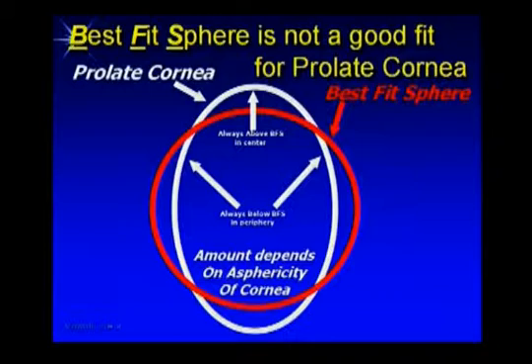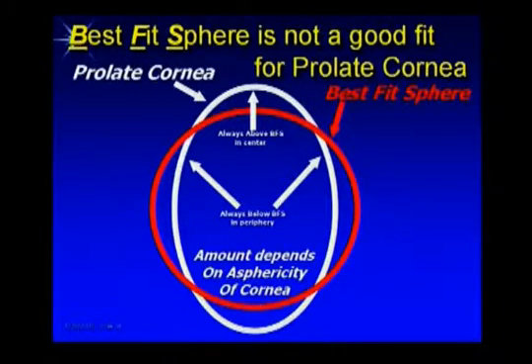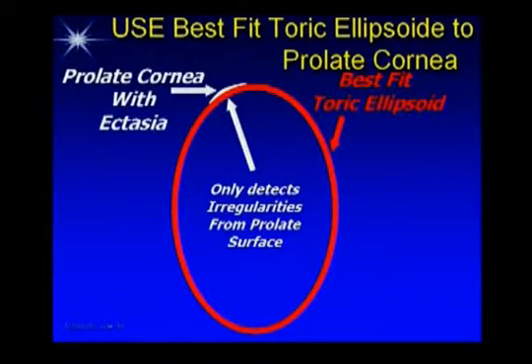For 25 years we've used a sphere as the reference for elevation above and below when looking at corneal data. But the cornea is not a sphere — it's an ellipse, an oval or football shape. Because we've used a sphere, trying to fit a basketball to a football, the central cornea always appears higher and the periphery always appears lower. The variation in elevation above the sphere can be 10 to 30 microns solely due to asphericity. If we instead fit with a toric ellipsoid — the ellipse that best fits the cornea — only true irregularities on the surface show up, both front and back.